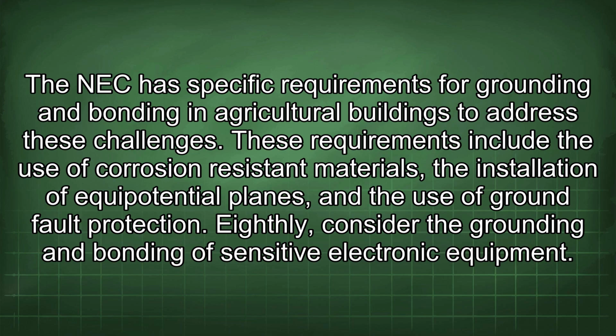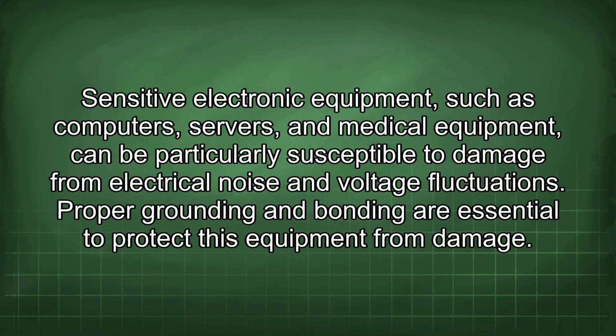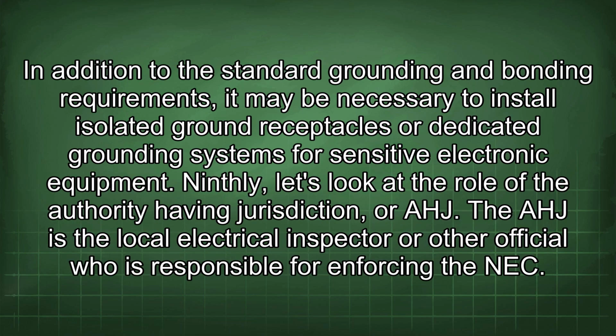Eighthly, consider the grounding and bonding of sensitive electronic equipment. Sensitive electronic equipment, such as computers, servers, and medical equipment, can be particularly susceptible to damage from electrical noise and voltage fluctuations. Proper grounding and bonding are essential to protect this equipment from damage. In addition to the standard grounding and bonding requirements, it may be necessary to install isolated ground receptacles or dedicated grounding systems for sensitive electronic equipment.